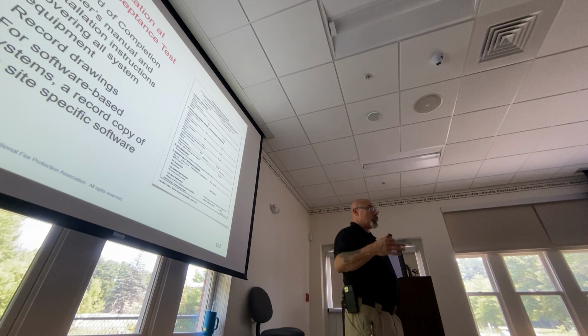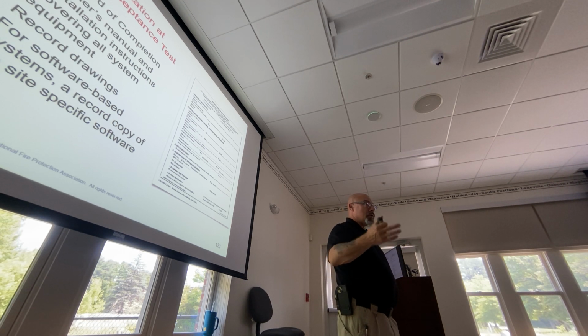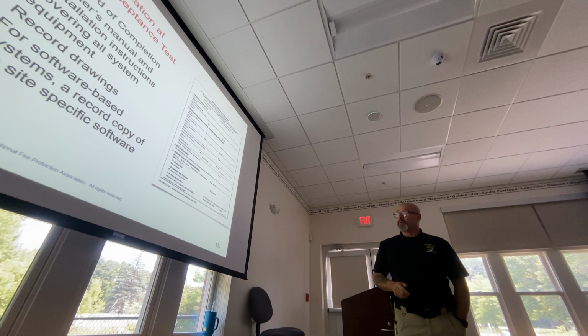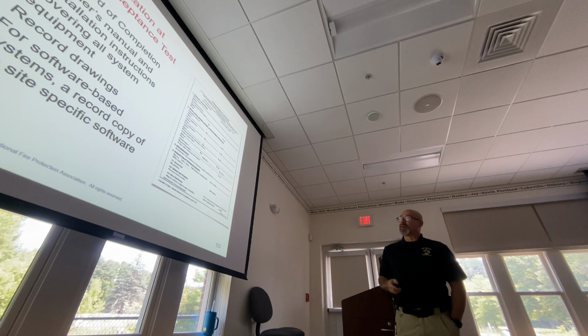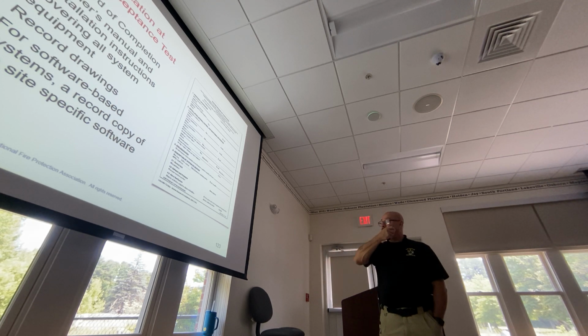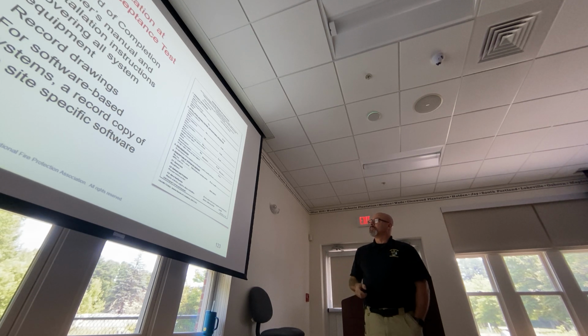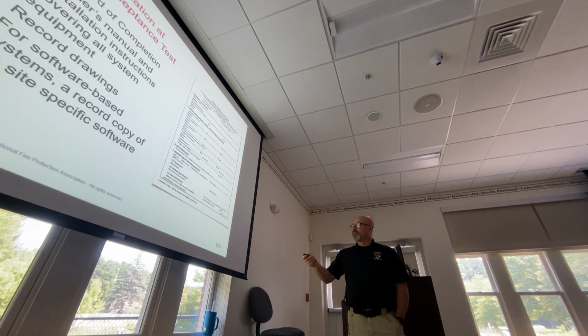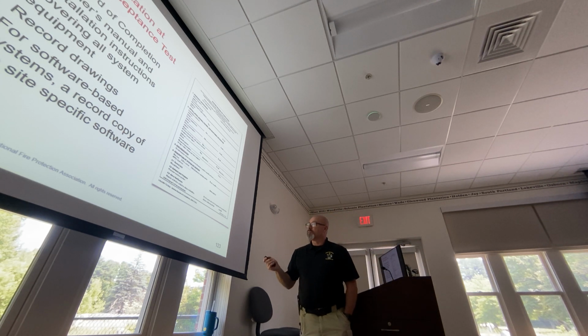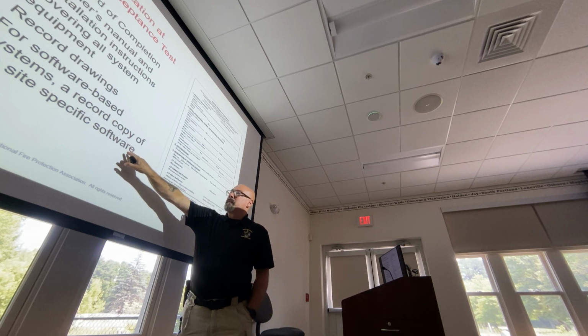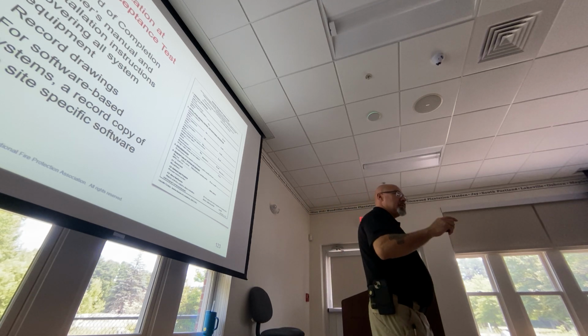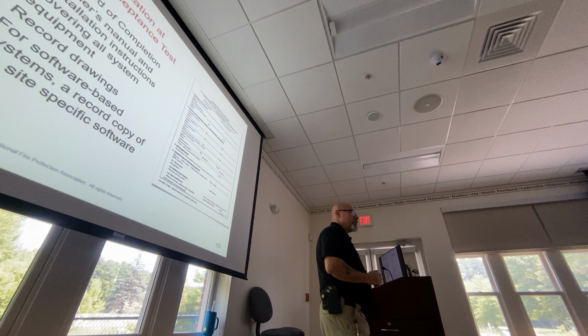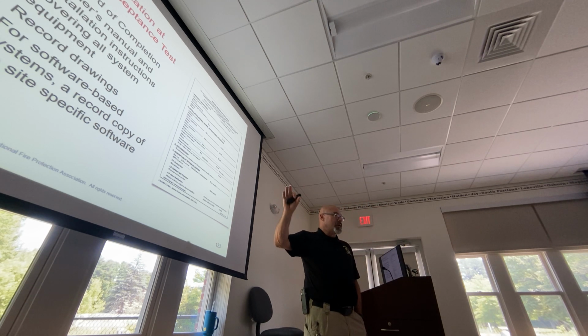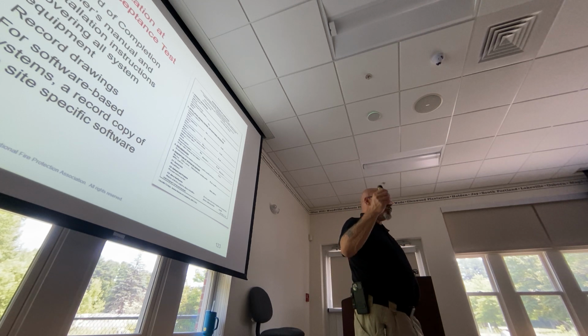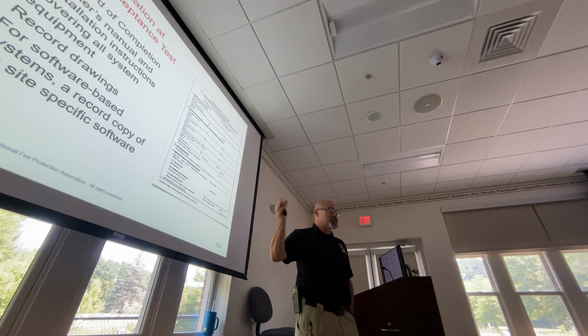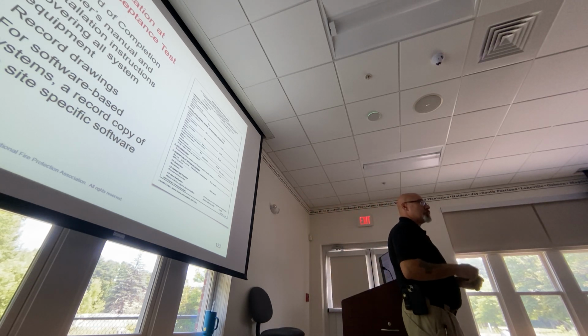Documents are super important with a fire alarm system. The design of that, all the documents that go along with it, indicating what the devices are, very important to have all of that. Should have the record drawings, the as-built drawings should be the final set. Description of system or service, how they're using it, software or firmware information, alarm verification, make sure everything works. For software-based systems, there should be a thumb drive, CD, or something kept. The owner should have a copy of that, because if that system should fail, they should be able to completely rebuild and reboot the system, kind of like a flash drive. You flash the system, reboot it, get it back up and running just as it was designed.